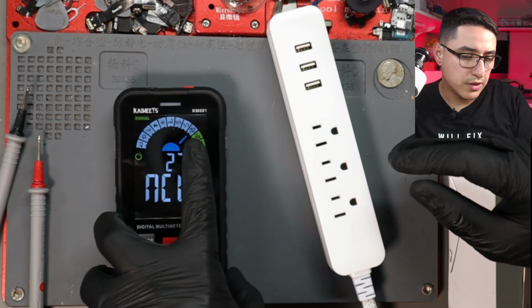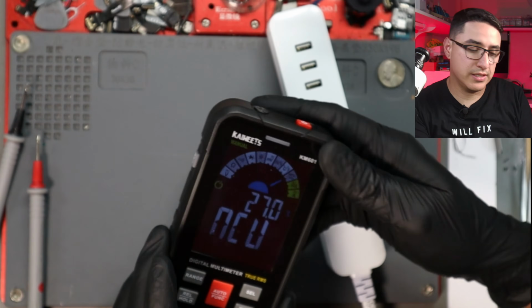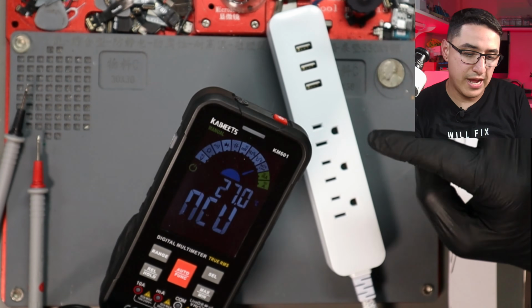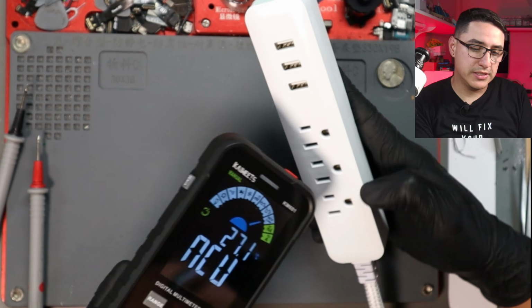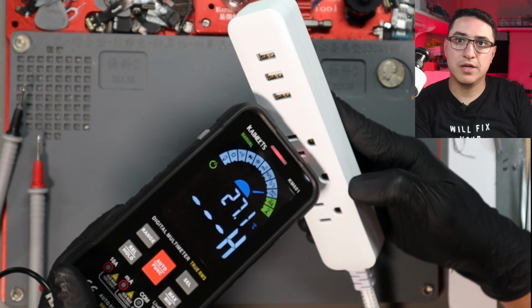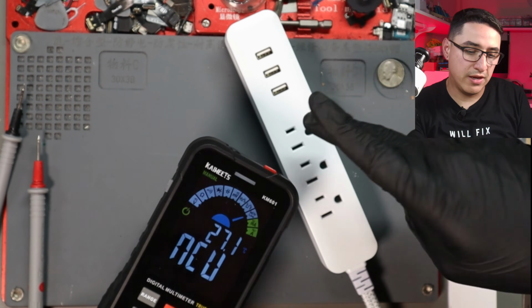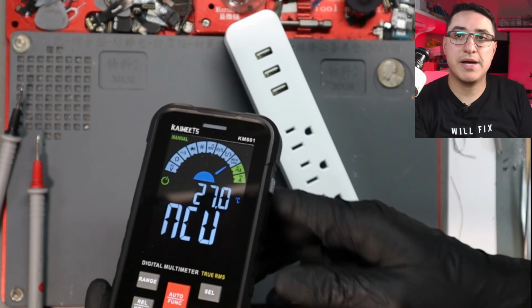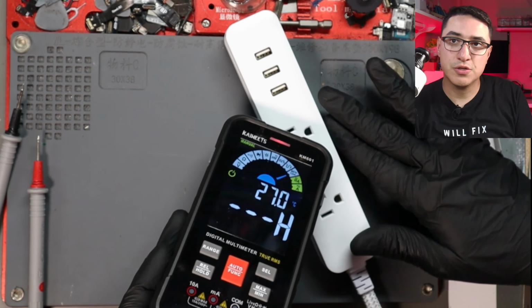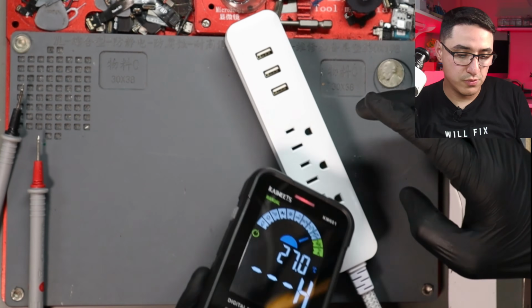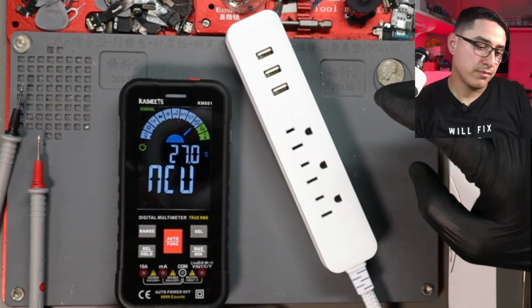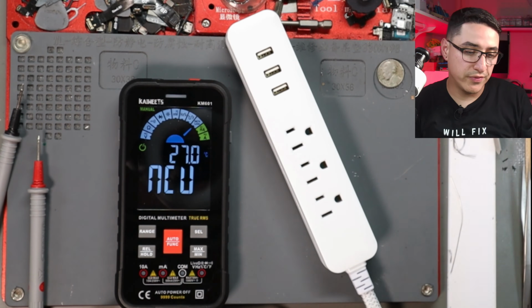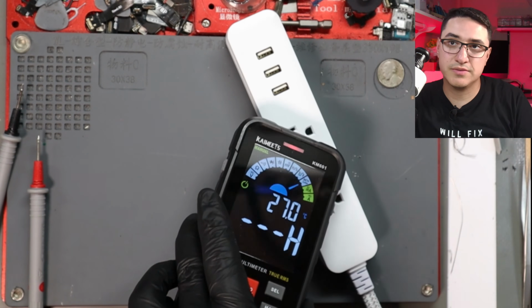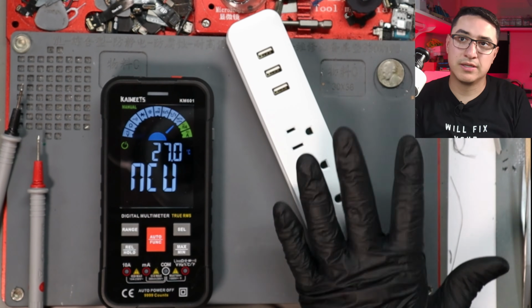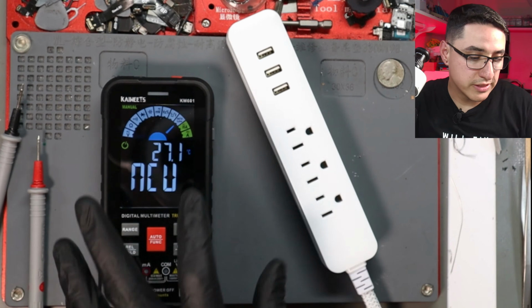Now we're going to do non-contact voltage. This is where you can check to see if there's any live voltage at an outlet, whether or not it's hot. So if you want to check if an outlet is broken, or if, let's say, you flip the breaker switch on your electrical panel and you want to make sure there's no live voltage there, this is the way to do it. You don't want to be touching wires if you're not 100% positive that there's no power there. So it's a huge thing for safety.